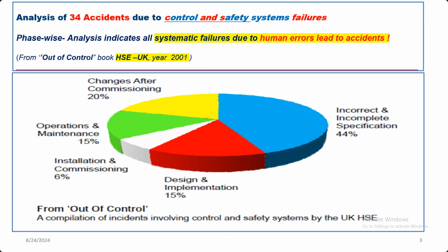Installation and commissioning is 6%. Operation and maintenance, I'll give you an example: if you are taking out any sensor or control valve for calibration, and a mistake is made during the calibration by the instrument technician or the foreman, whoever he may be, then that type of mistake has led to 15% of the accidents. From the operation point of view also, in BPCS, normally DCS based, on any controller the operator is free to change the mode from auto to manual. If he finds that in auto mode the controller is not functioning all right, he will take it to manual and try to control it. And in that process, if he forgets to change back to auto mode, incidents have been reported to result in disaster accidents.